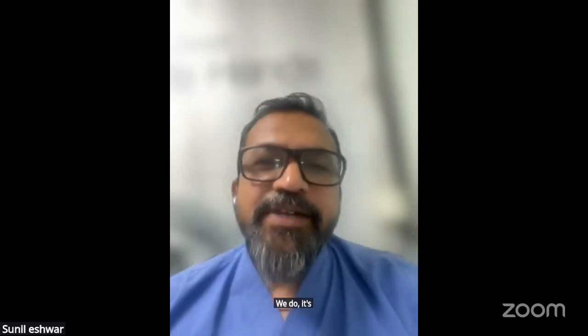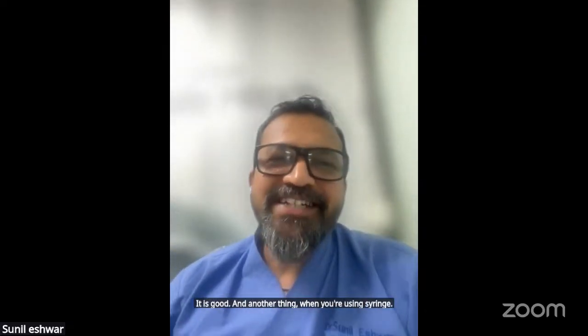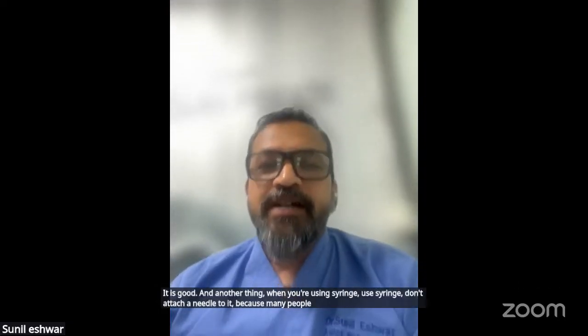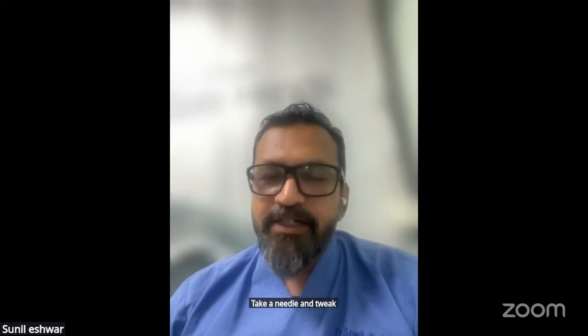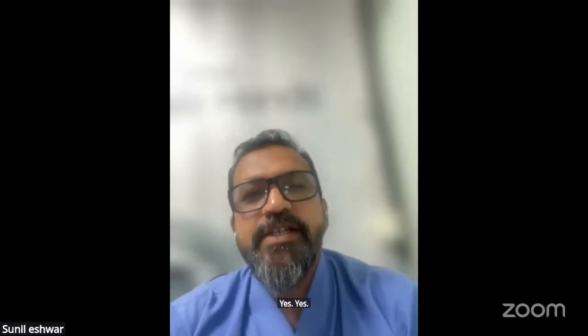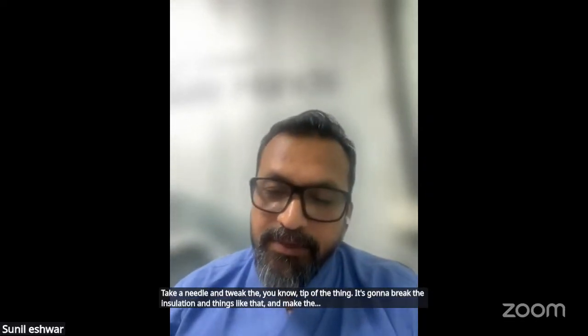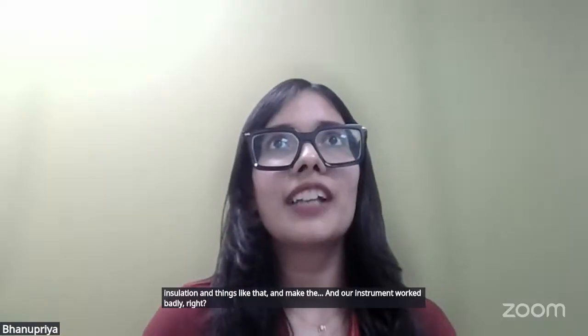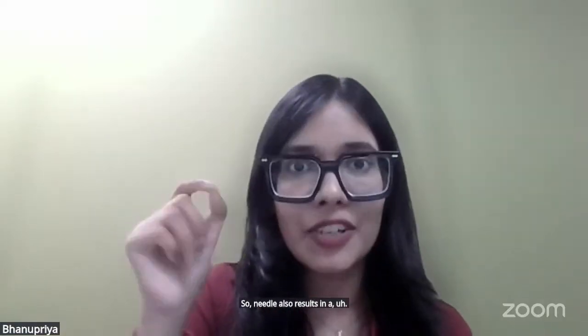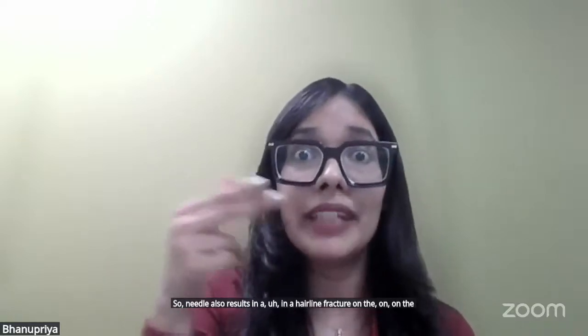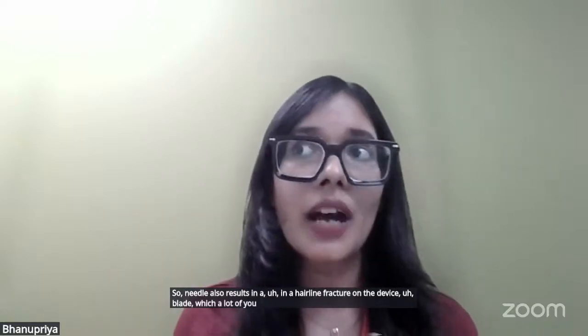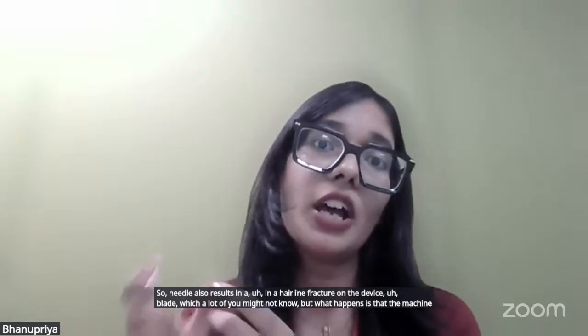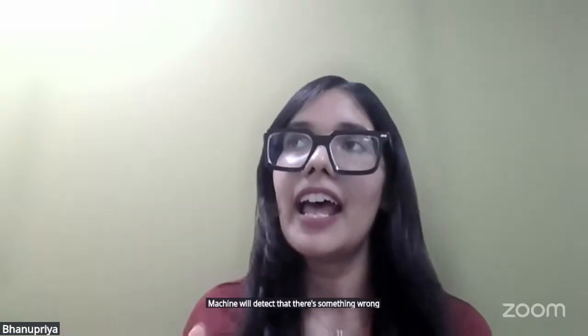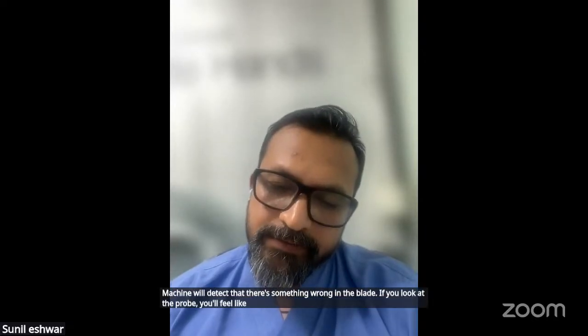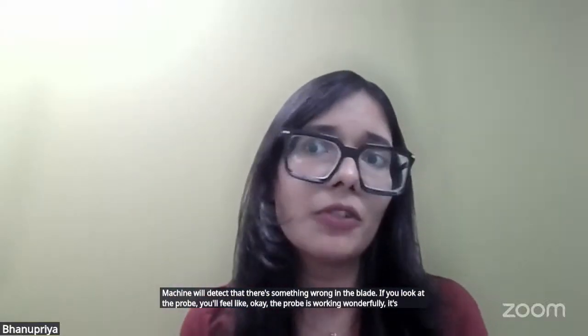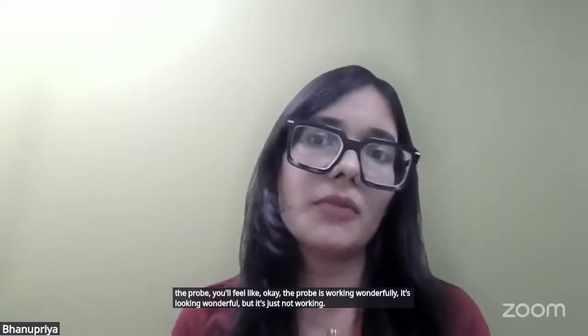Thank you, Bhanu. Another thing: when you are using a syringe, don't attach a needle to it, because many people do that, taking a needle and tweaking the tip. It is going to break the insulation and make the instrument work badly. A needle also results in a hairline fracture on the device blade, which a lot of you might not know. The machine is very sensitive and will detect that something is wrong in the blade. If you look at the probe, you will feel it is looking wonderful, but it is just not working. There is some issue with the machine.